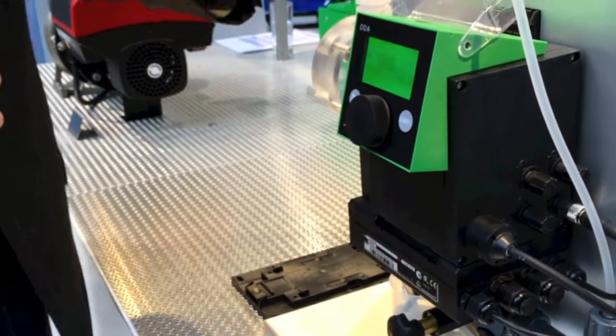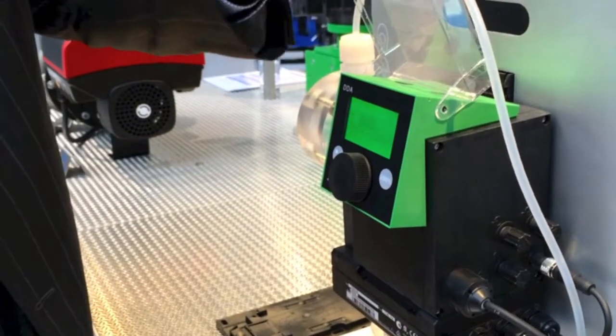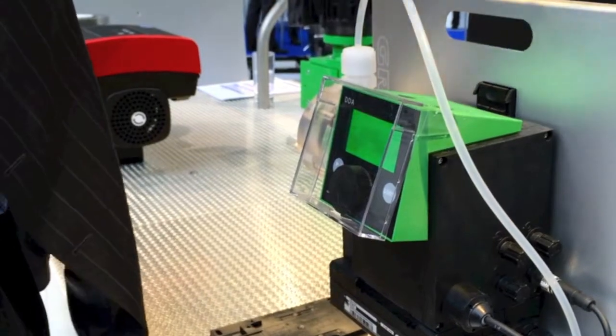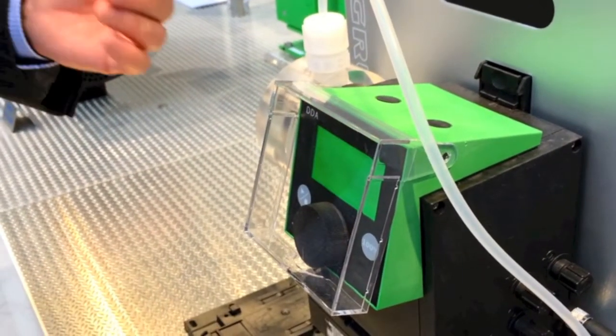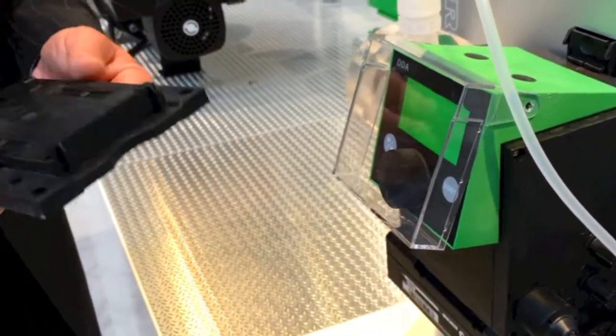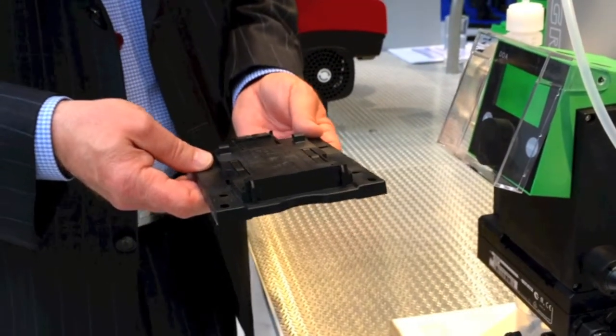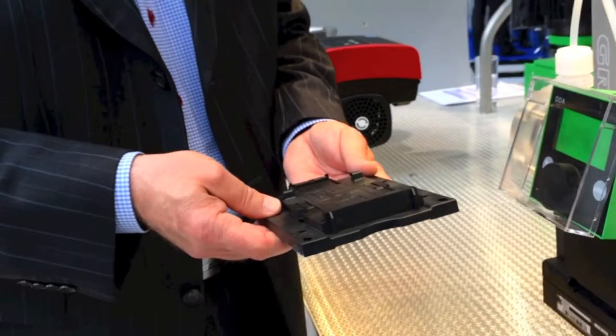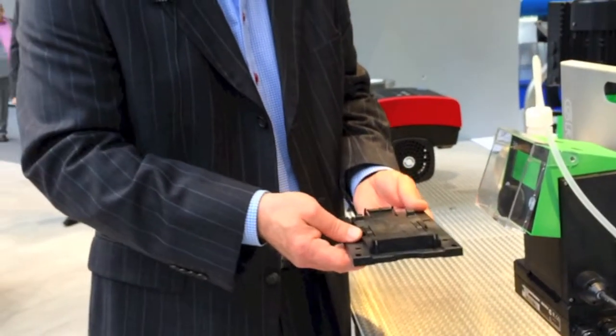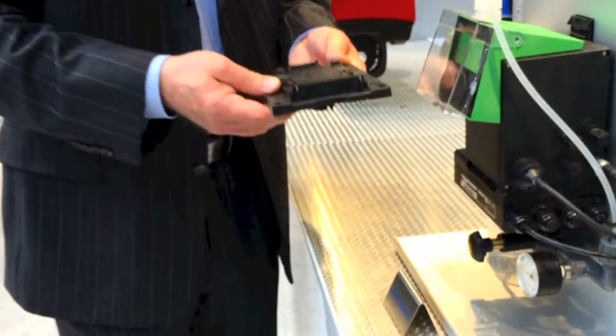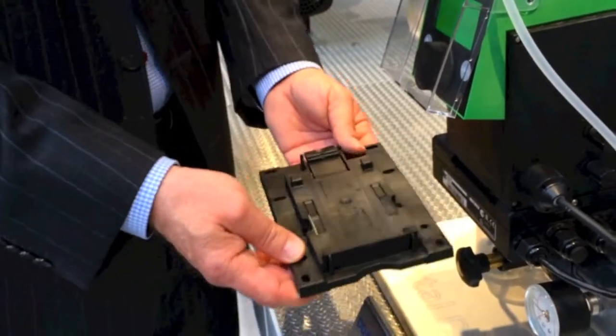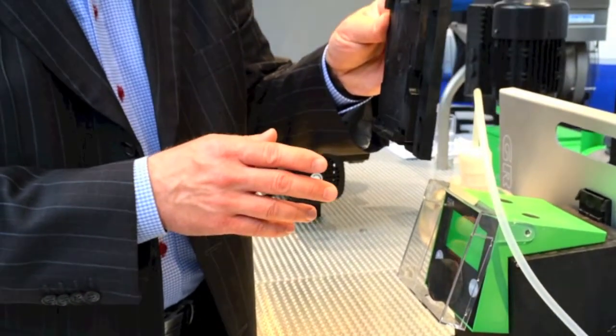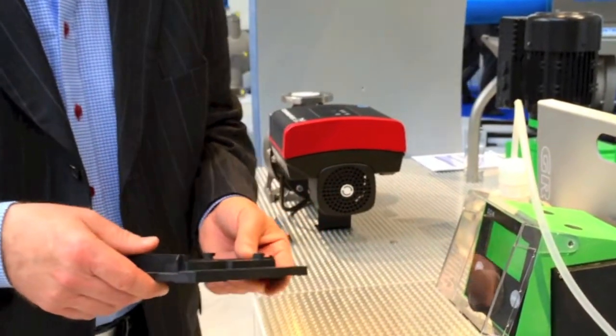With our Smart Digital, you can turn the control cube into three positions. If you remove these two screws, you can turn the control cube into three different positions with one product number. The other thing is this base plate, which can also be mounted in two different positions. You can install it on the floor, or you can remove it from the pump, screw it on the wall, and hang the pump into this holder. So with the Smart Digital, you have seven different installing positions with one product number, and that is a big benefit.